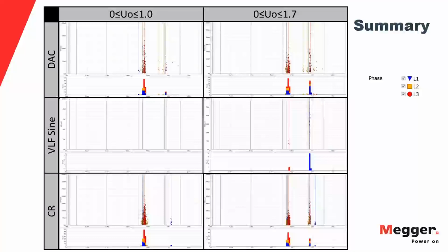It's called MIND. It's mass impregnated non-draining. It's very similar to PILC. And because it was not very high in magnitude and not very concentrated, it was pretty much left alone, so nobody opened the cable at that spot.